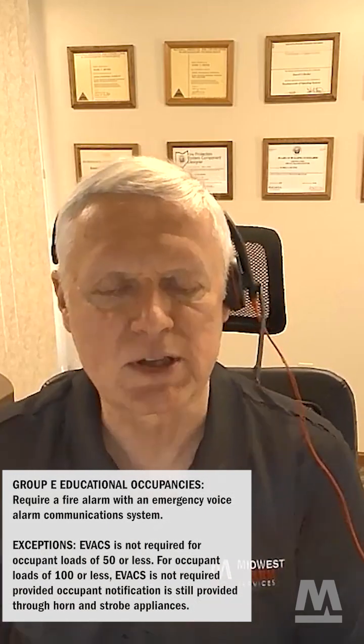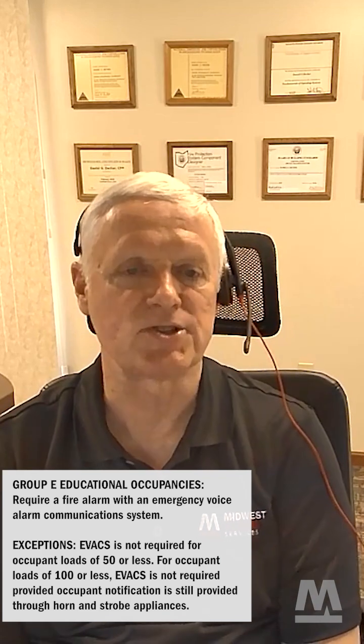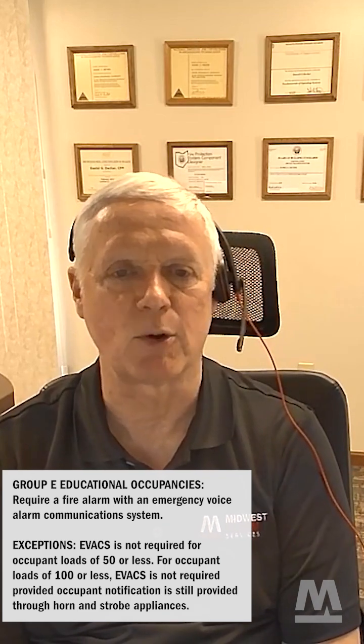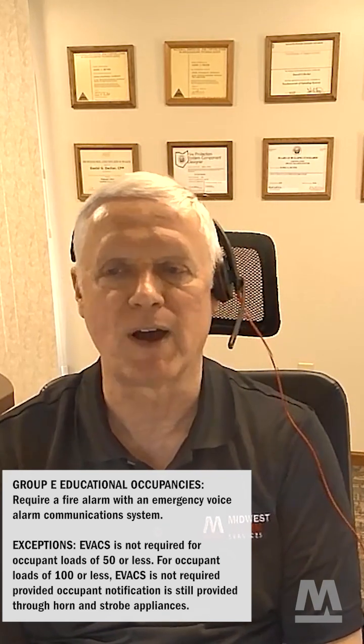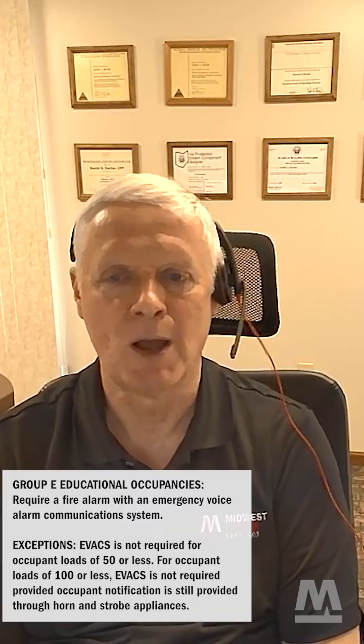For occupant loads of 100 or less, evacs is not required, provided the occupant notification is still provided through horns and strobes. So we've kind of got a tiered approach. You have to have a fire alarm system in a Group E occupancy. If it is under 100 occupants, it can be done with horn strobes. And if it is over 100, then yes, you're into an emergency voice alarm communication system.